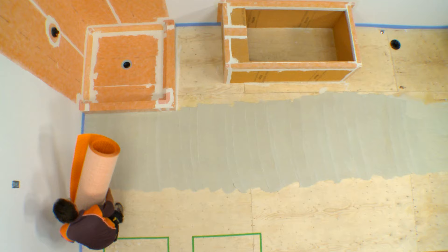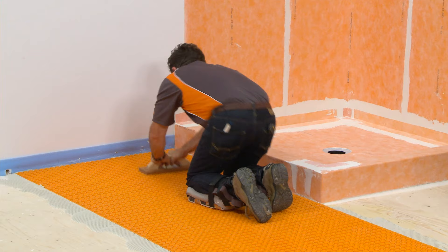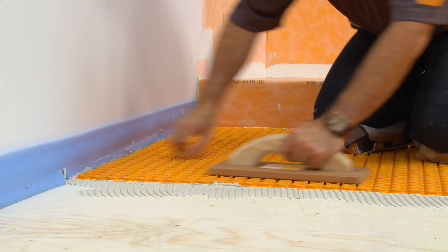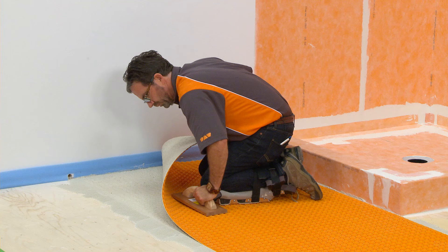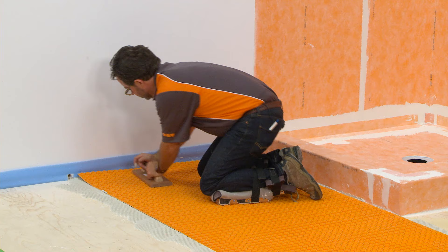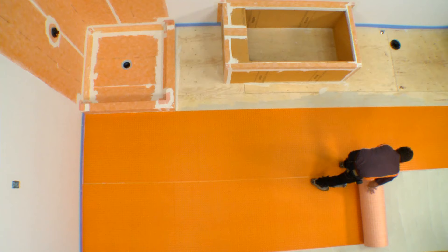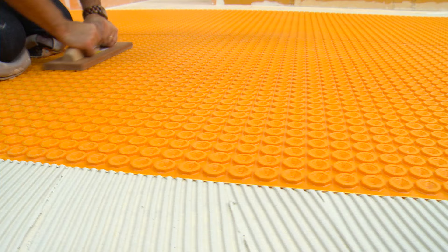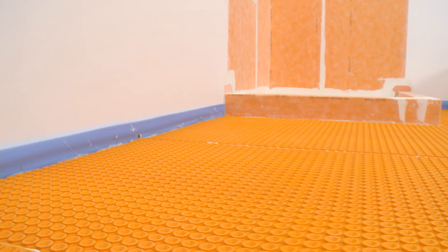Apply the Ditra-Heat fleece side down and solidly embed in the mortar using a float or the Ditra roller. Lift up a corner of the membrane to check coverage. Proper installation results in full contact between the fleece webbing and the thinset mortar. Re-embed the membrane. Aligning the studs between adjacent sheets will make subsequent heating cable installation easier. Once complete, replace the tape to mark the areas where fixtures will be placed. The installation of the Ditra-Heat is now complete.